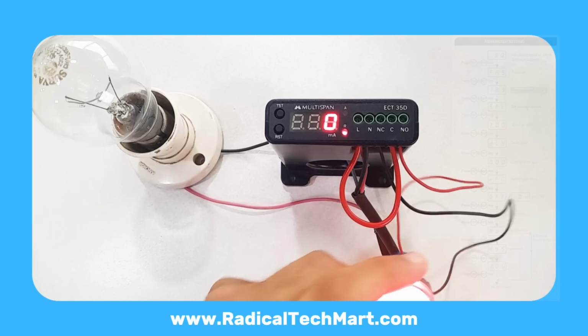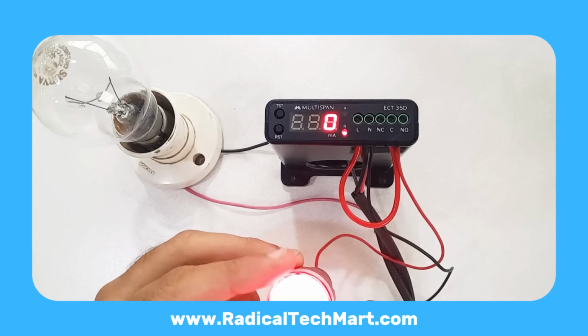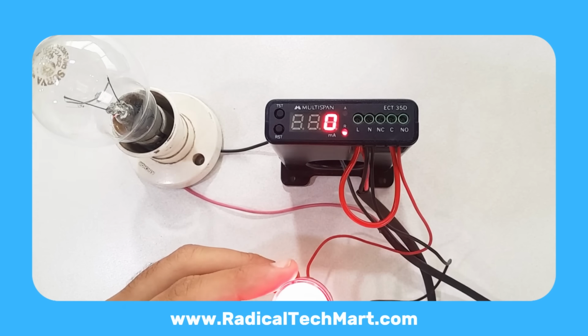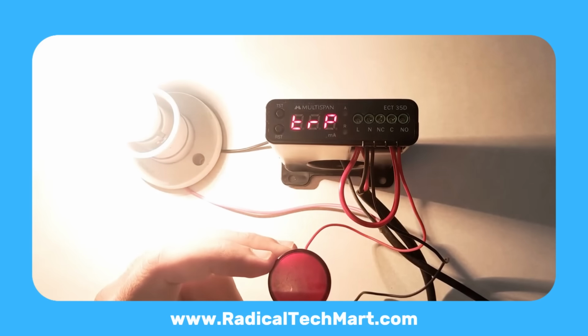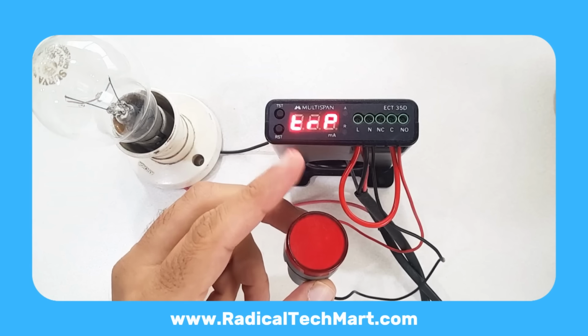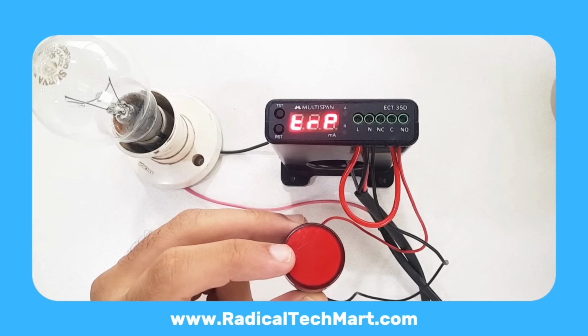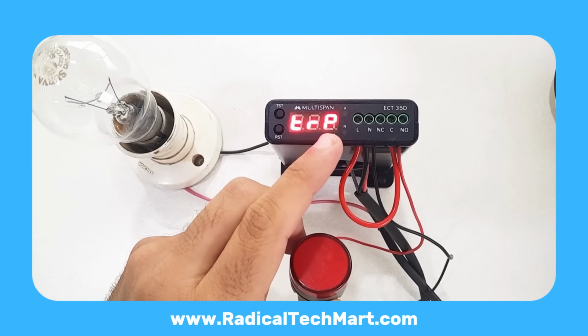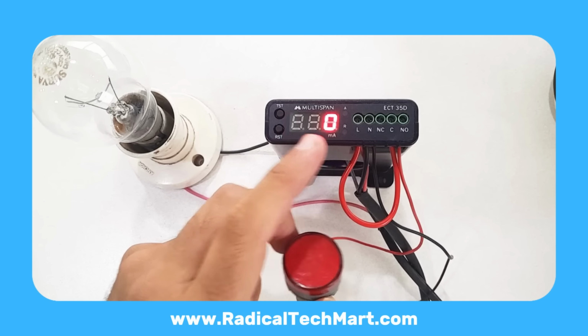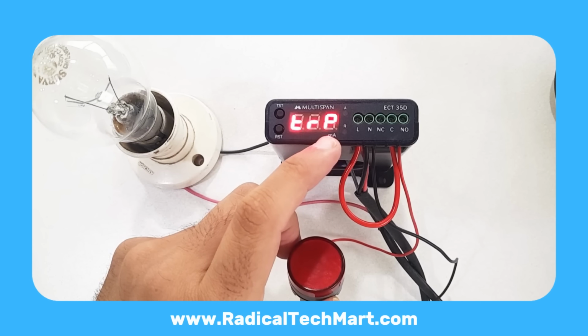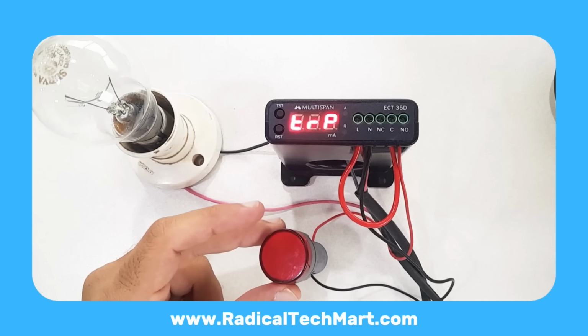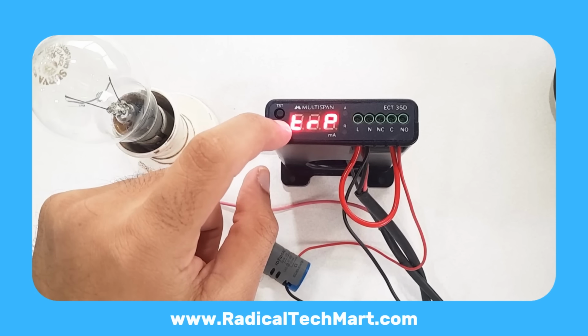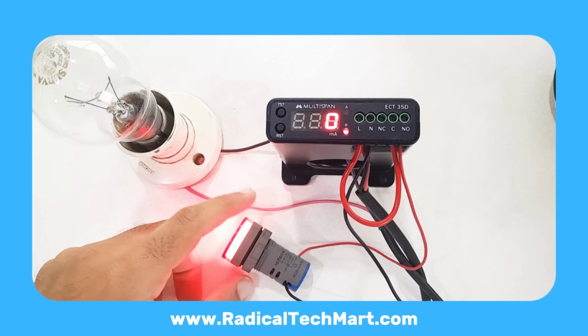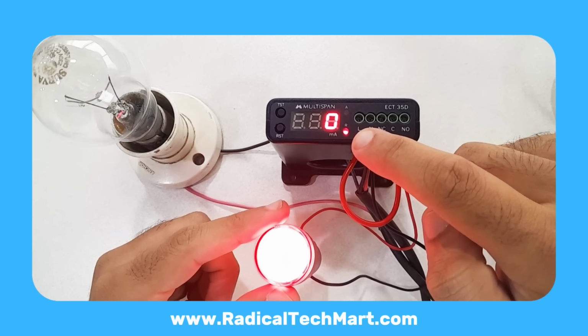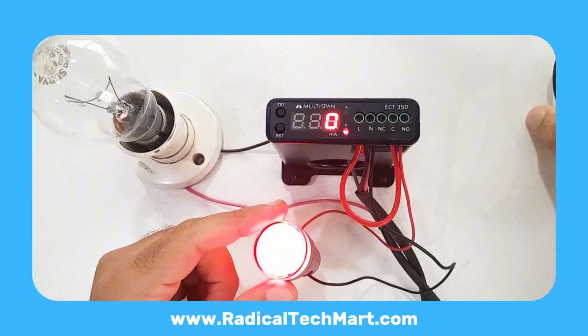Now, let's test it live. We've set the delay to 0 seconds. When I switch on the bulb, the leakage current is immediately detected, and the controller trips the relay. You'll see the trip indicator LED turn on, and the relay output LED turn off. The display also shows the actual leakage current value, for example, 434 milliamperes. When the bulb turns off, the leakage drops back to 0. Since we're in manual mode, we now press reset to clear the trip condition, and the relay turns on again.